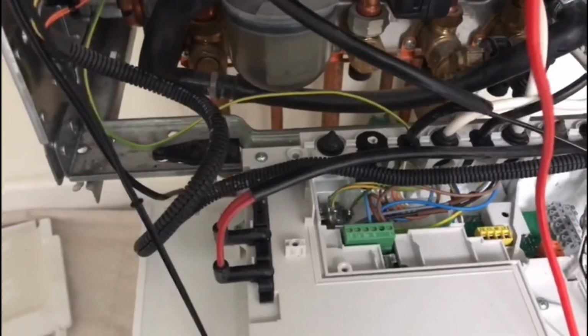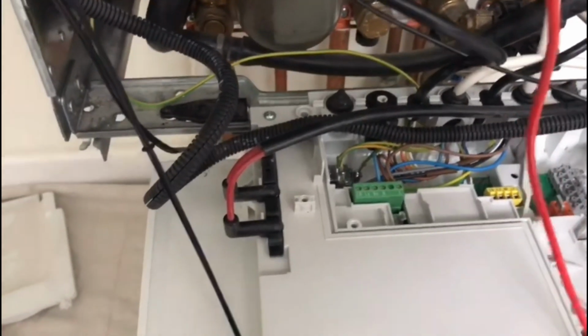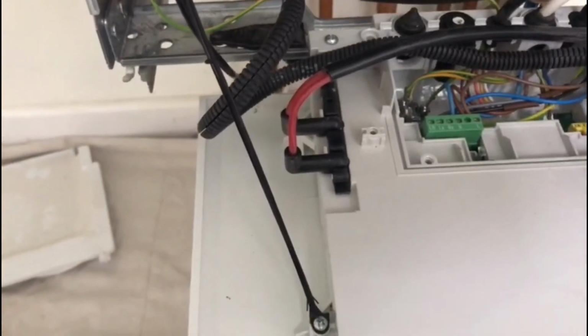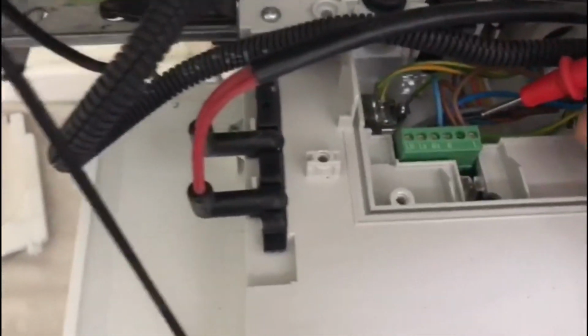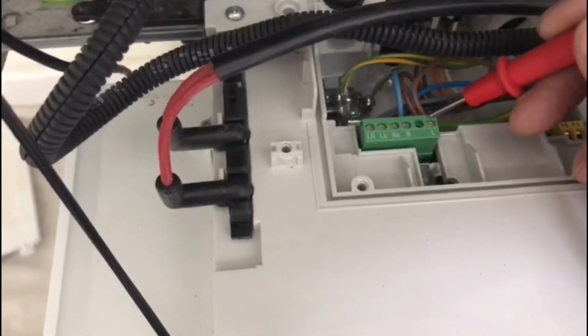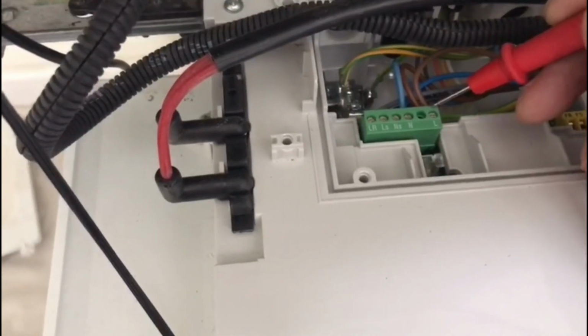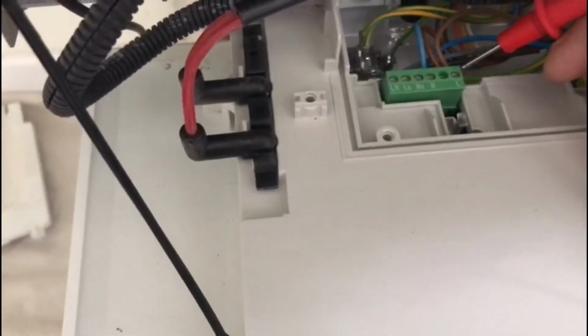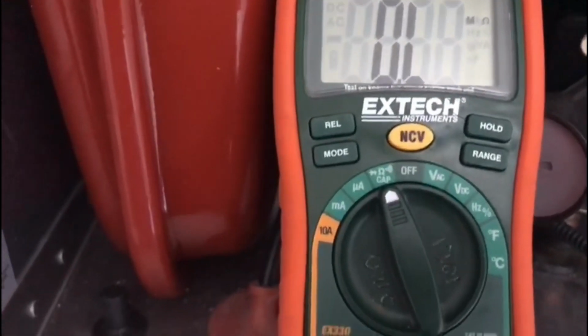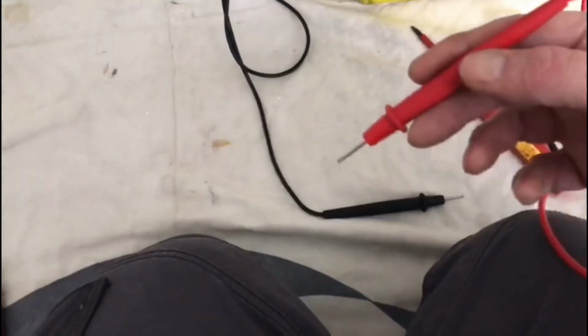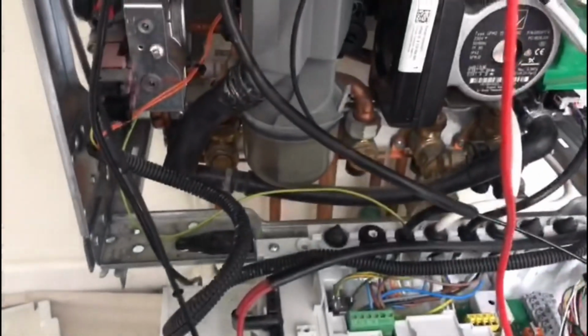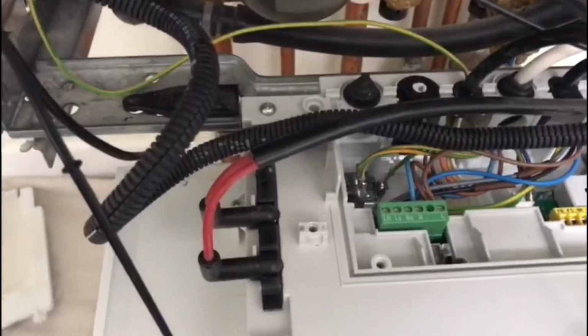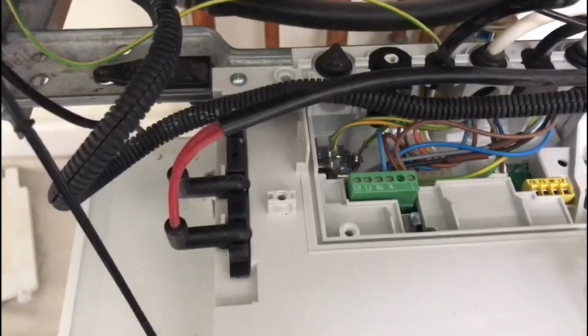Next, checking for a readable resistance on the boiler, or short circuit test. What you should do is test from your live, just here, across all your neutrals, and that will tell you if you've got a short circuit or not. You should be having a readable resistance in ohms. Open line means that there's a break, there's nothing connected, because my probes aren't currently touching. Now if you test on a short circuit test and you've got continuity, like your base reading on your multimeter, there is a problem.